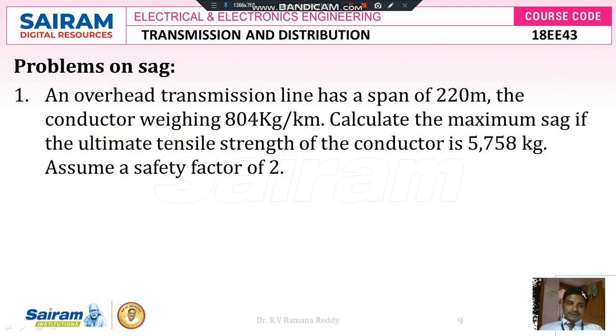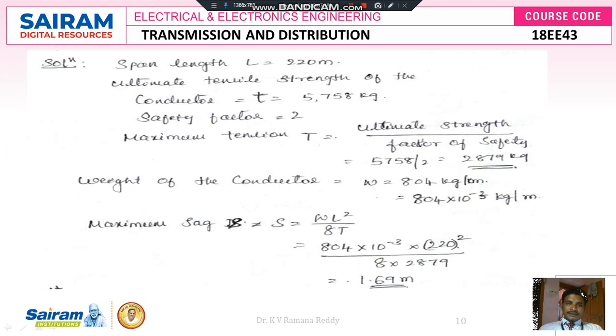Problem 1: An overhead transmission line has a span of 220 meters. The conductor weighs 804 kg per kilometer. Calculate the maximum sag if the ultimate tensile strength of the conductor is 5758 kg. Assume a safety factor of 2. Given: span length L = 220 meters, ultimate tensile strength = 5758 kg, safety factor = 2. Therefore, maximum tension T = 5758/2 = 2879 kg.